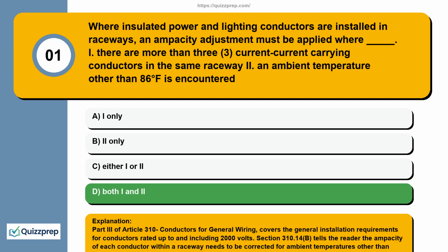Part 3 of Article 310, Conductors for General Wiring, covers the general installation requirements for conductors rated up to and including 2000 volts. Section 310.14(B) tells the reader the ampacity of each conductor within a raceway needs to be corrected for ambient temperatures other than 30 degrees Celsius, 86 degrees Fahrenheit. Also, Section 310.14(C) tells us the ampacity of each conductor is to be adjusted as shown in Table 310.15(C)(1) where the number of current carrying conductors within a raceway or cable exceeds 3.